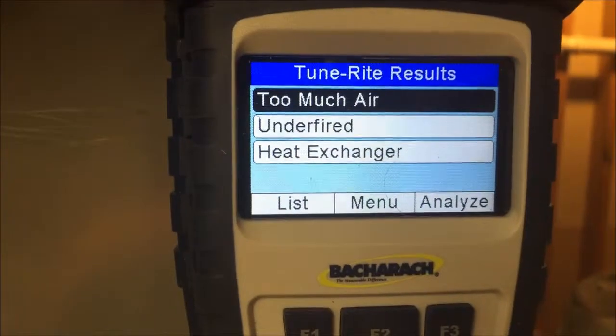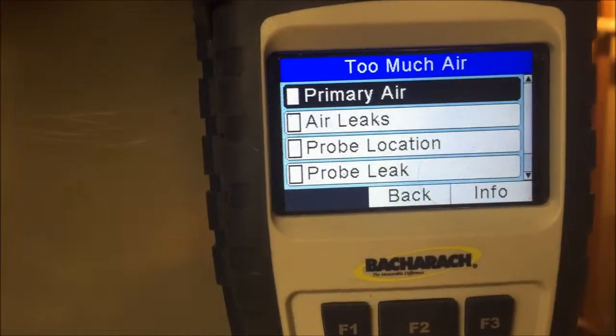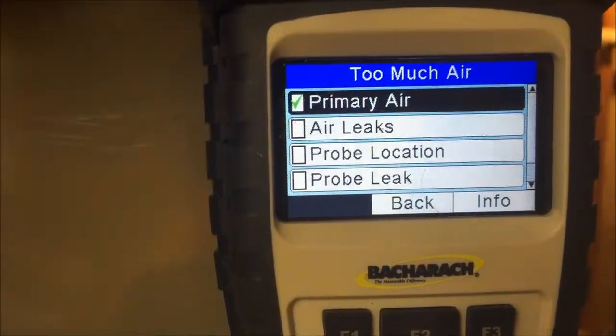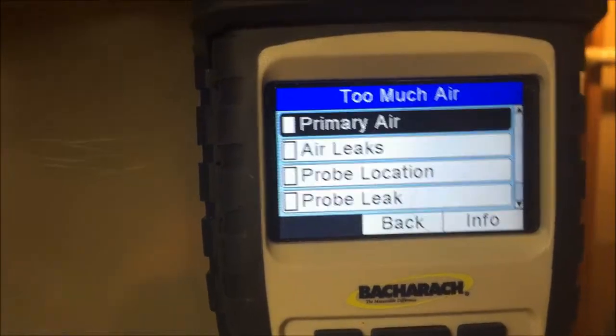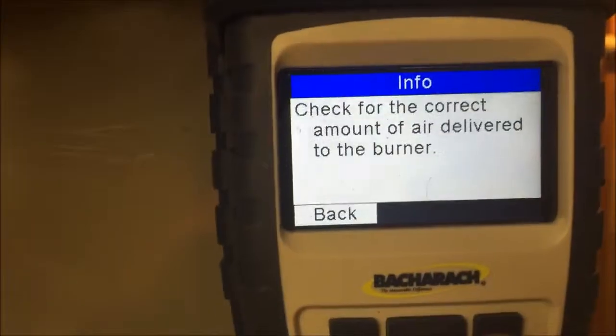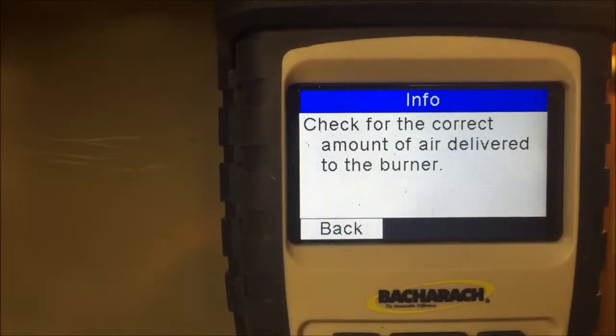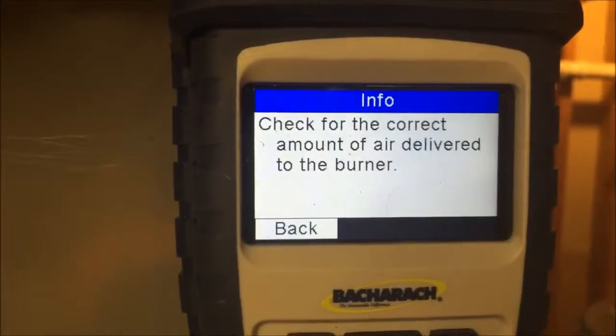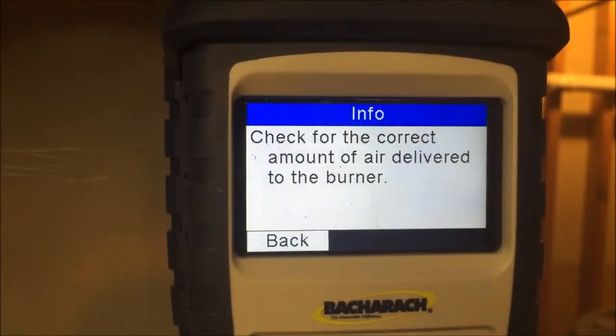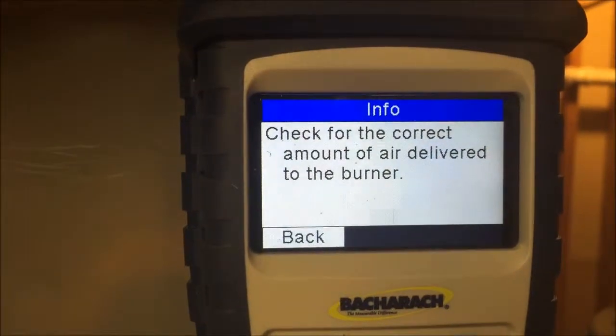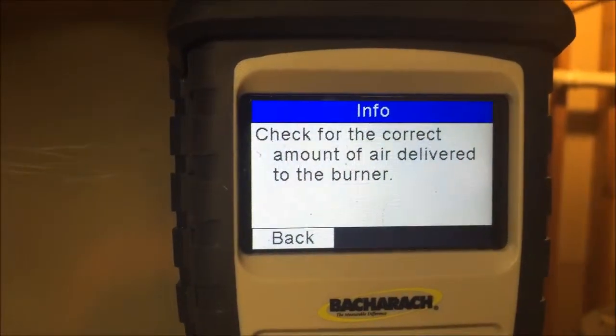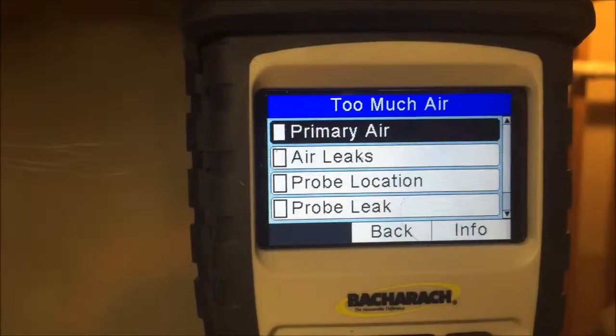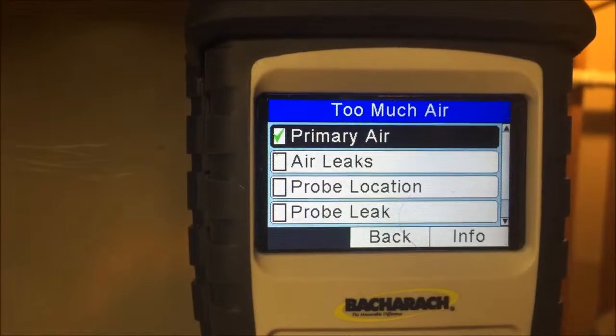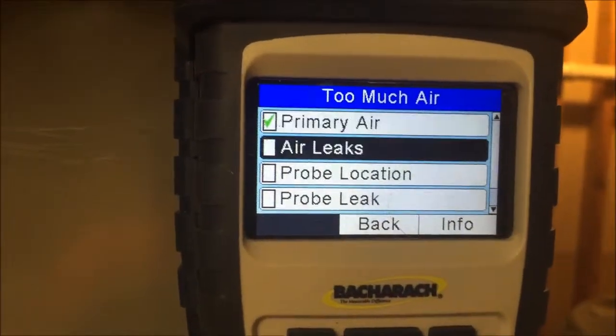All right, underfired. That's too much air. Primary air. Hit enter again. Or info. Check for the correct amount of air delivered to the burner. Okay, I know my primary air is good. It's an unadjustable burner, so I'm not going to worry about that.